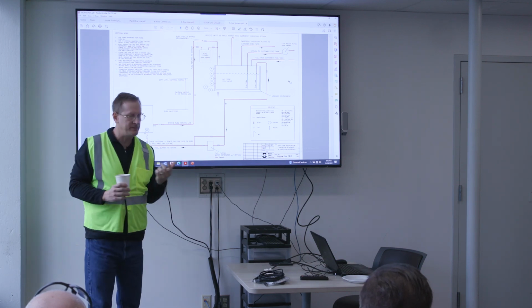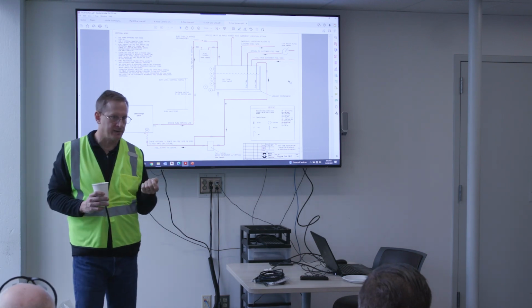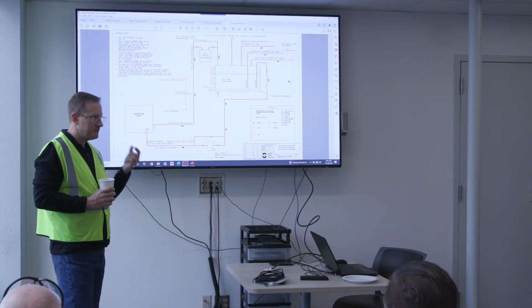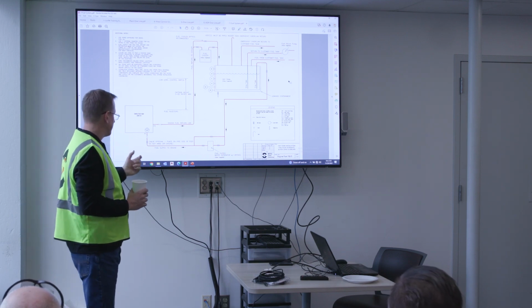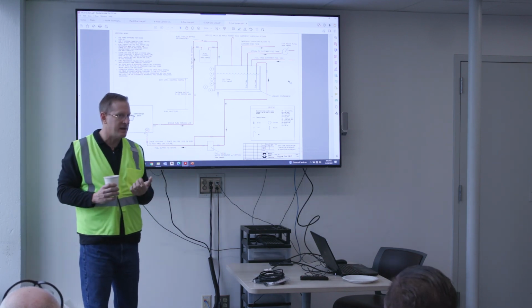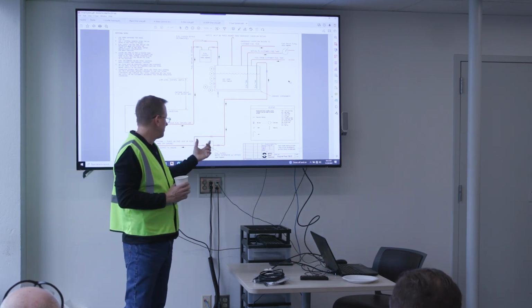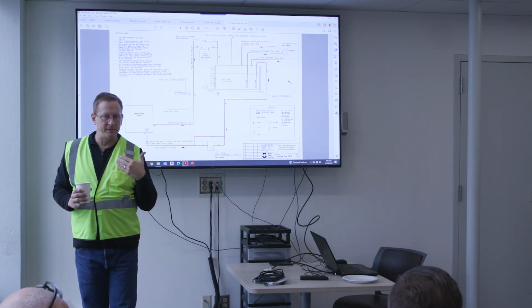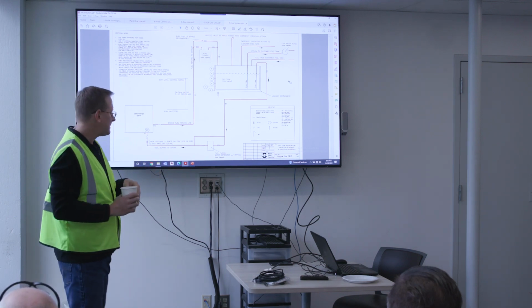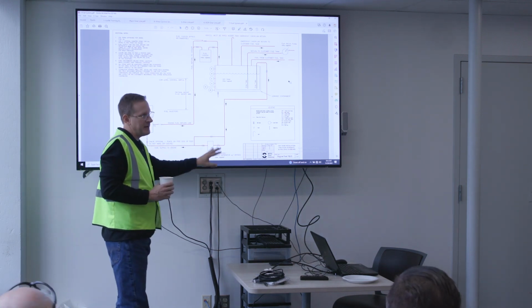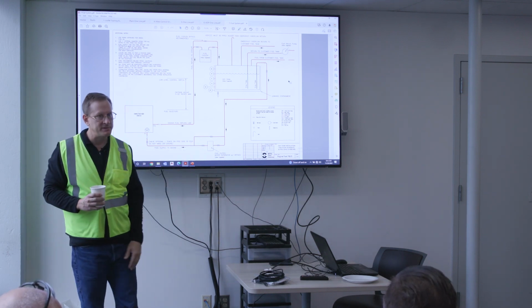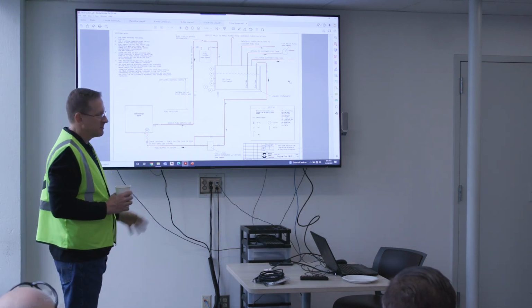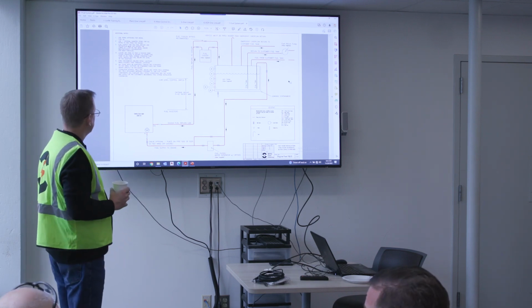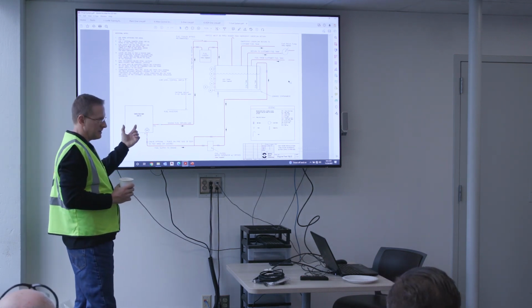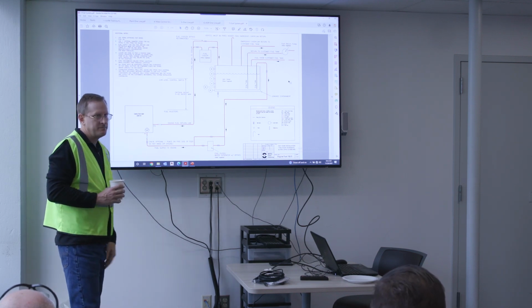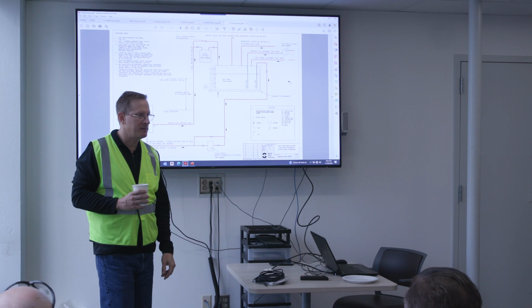We actually have 2 pre-filters, in fact. One of them is actually on the engine itself, attached to the frame just in front of the engine. The other fuel filter water separator has not been delivered yet. So as soon as it arrives, it'll be placed in line as well. The system is perfectly fine with the pre-filter that it has now. This is a redundant fuel filter that we put on our systems, and once it arrives, it'll be put in as well. It had some supply chain issues with that particular filter. The engine also has its own engine fuel filter, so you're going to have filtration in triplicate once it's all said and done.